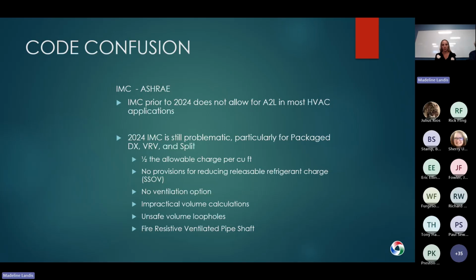There are no provisions at all for reducing releasable refrigerant charge, such as safety shutoff valves. There's no option for just ventilation of the space other than a full mechanical room. It's kind of impractical and, really, I'd say unsafe volume calculations that allow you to use some loopholes. It was one thing to do that with an A1 refrigerant, but now that we're talking semi-flammables, we really shouldn't use those loopholes that forget about the actual weight of the refrigerant. Oh, and the ventilated pipe shaft. I'm sorry, that last one is a biggie in the IMC.